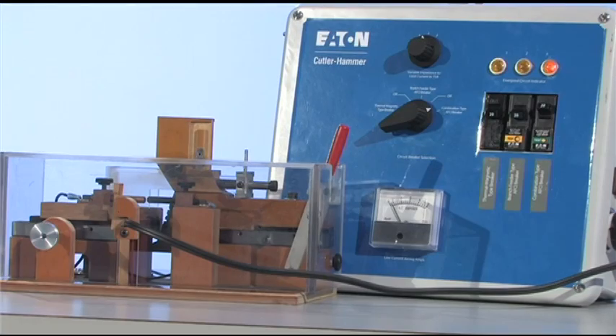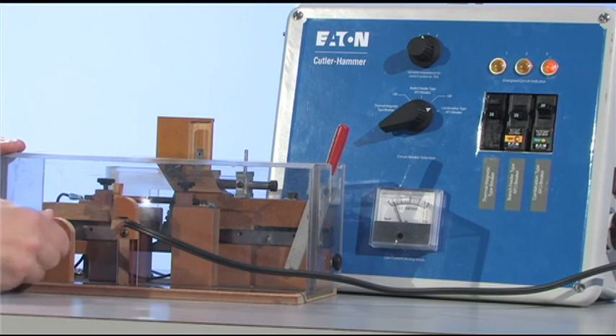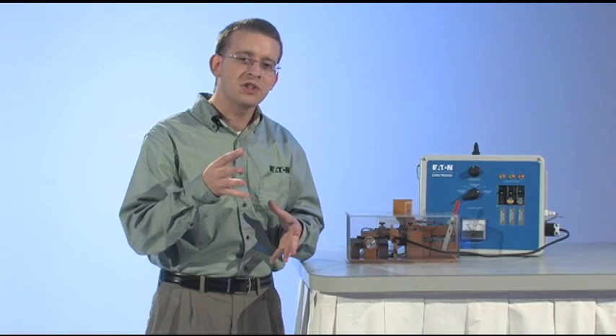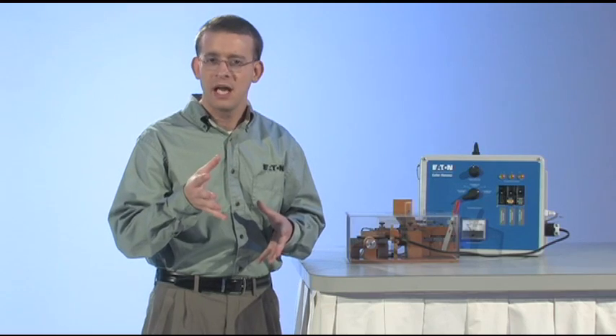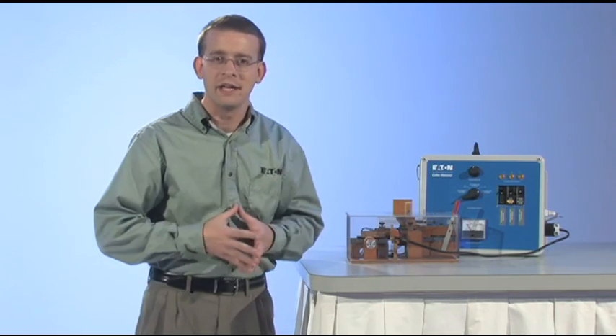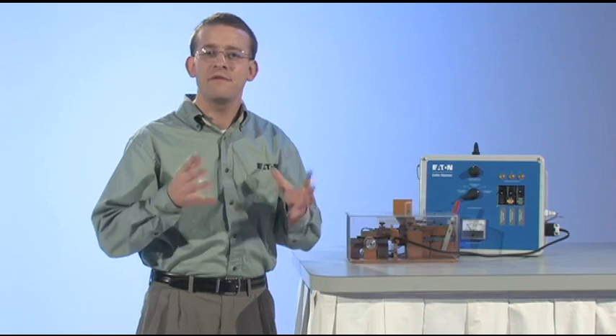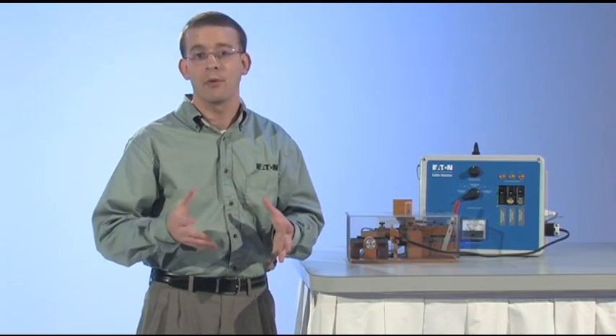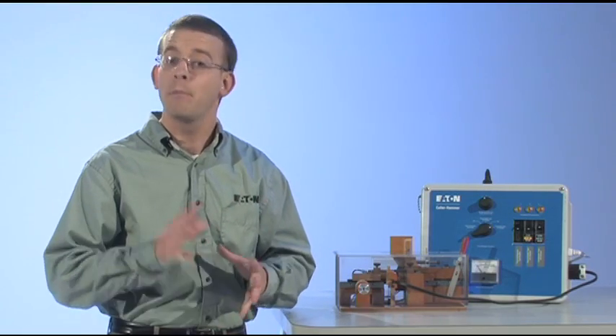The challenge with designing the combo AFCI breaker is that every electrical device will create arcs during their operation. When the contacts close or separate, they create these small arcs, just as I was trying in the demo here. The protective device needs to differentiate between these operational or intentional arcs, such as the flipping of a light switch or operation of a motor, and the non-operational or dangerous arc. The combo AFCI breaker is designed to ride through these operational arcs and only look for sustained low current arcing before tripping.